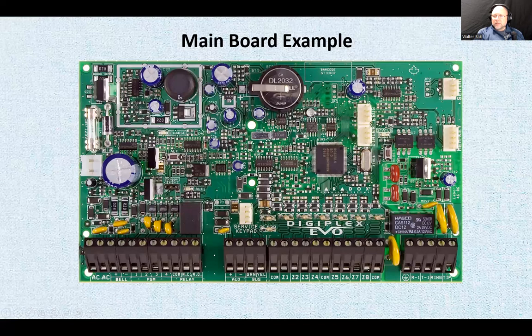Now also we have one of the more important connectors: a serial port. That's where you can connect your serial interface from your laptop. So you've got a serial interface connected to the USB of your laptop, and the other part of the serial port is going to be connected to the serial port here. Then you can use the software designated for that particular main board to communicate and do the programming and setup. Because you can program the whole thing from the keypad, but it's just a long and treacherous process. With the laptop and the software, it becomes easy and more clear, and less confusing.